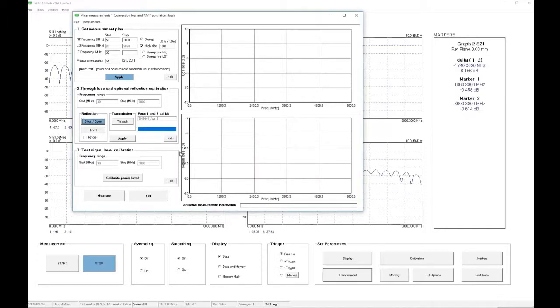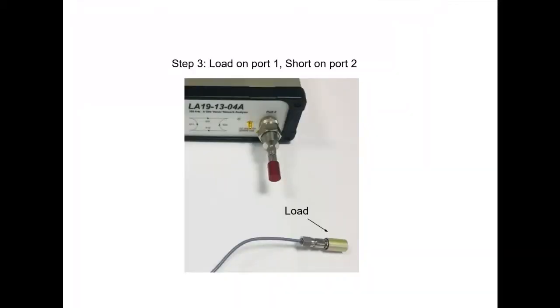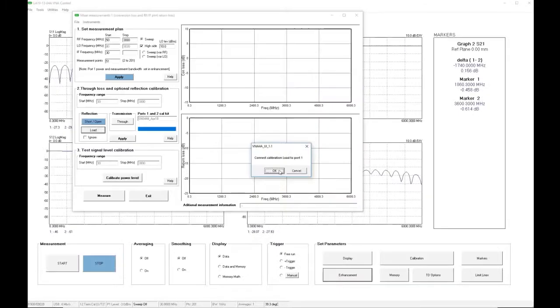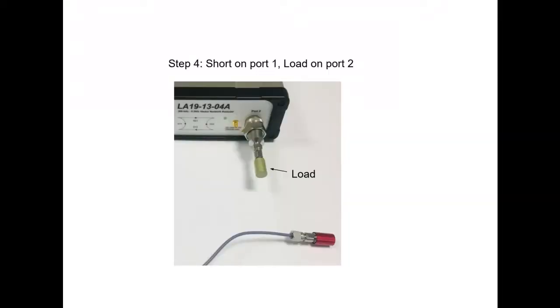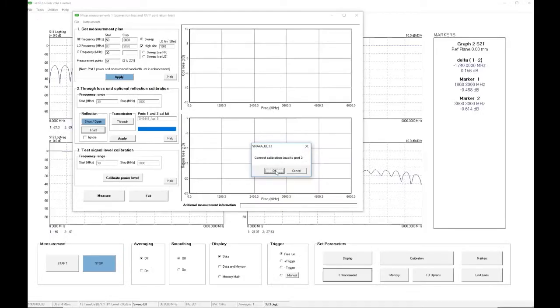Now we need to do the loads. So we click on Load, and the dialog tells us that we need to connect a load to port 1. And here we are. This is what we need to do. The load is connected to port 1, and whatever is connected to port 2 does not matter. Alright, so we click OK to make the measurement. We now need to connect the load to port 2. Alright, so here is what we need to do. And we click OK when we are ready to go. So now we have completed the reflection measurements.